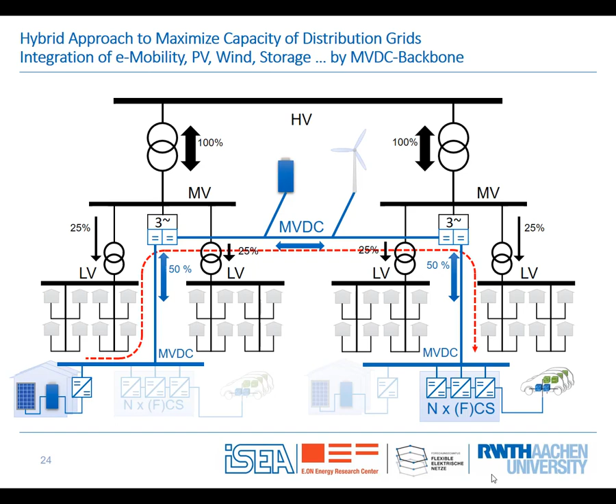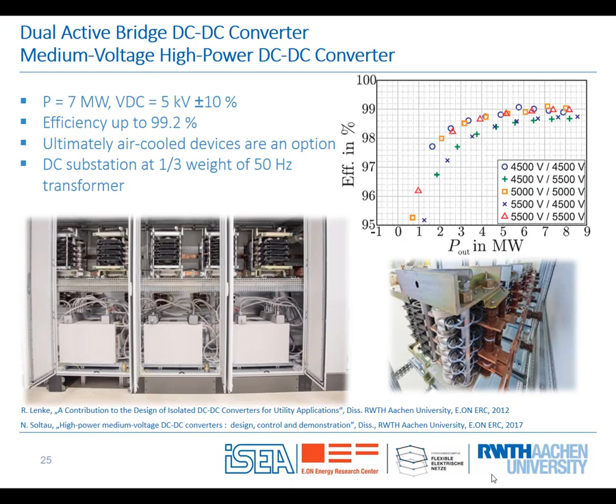The key enabling technology for that is what we call a dual active bridge, a bidirectional DC to DC converter. It consists of a standard three-phase inverter, actually stacks from ABB large drive systems, medium voltage. We have DC 5000 volt and three-phase transformers. In this case, we built in the first years 3 times single phase, then a three-phase inverter. The inverter never switches in PWM; it's controlled by phase shifting the input inverter versus the output, which is why we get very high efficiencies.